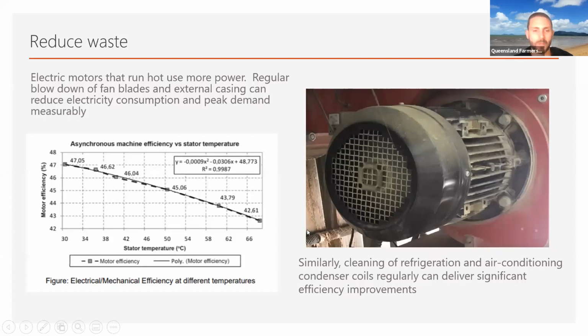And Randall, that could be a simple capacitor change on a single phase motor too, couldn't it? Like a general maintenance, yeah? Yeah, one of the points we made is that general maintenance on motors is well worth the small amount of capex. Your payback can be 6 or 7 times, just making sure it's operating efficiently, making sure that the capacitors are in good working order.